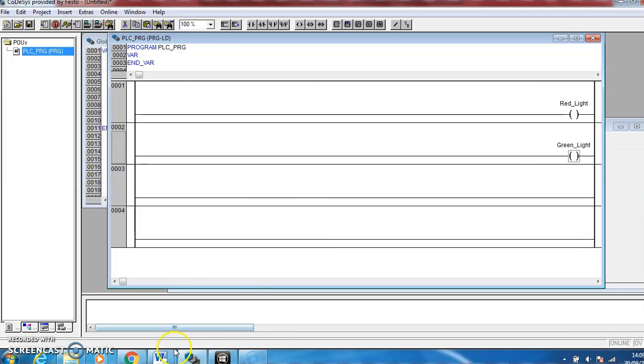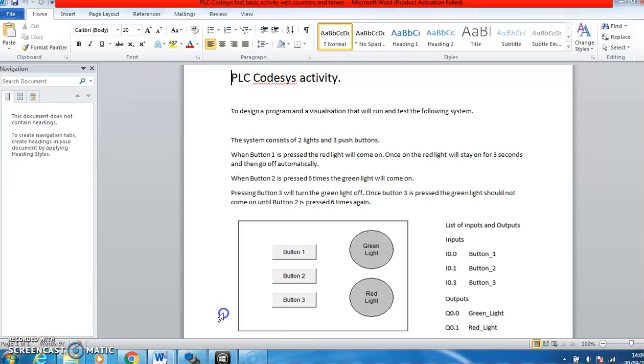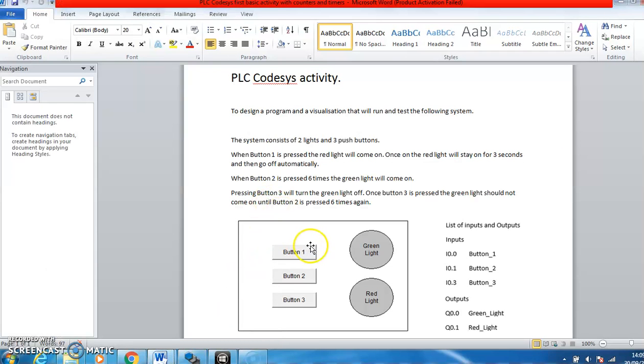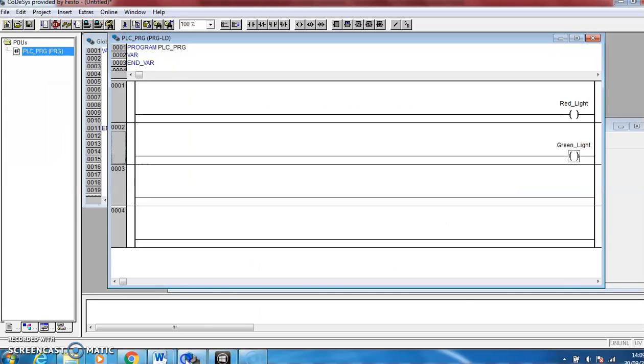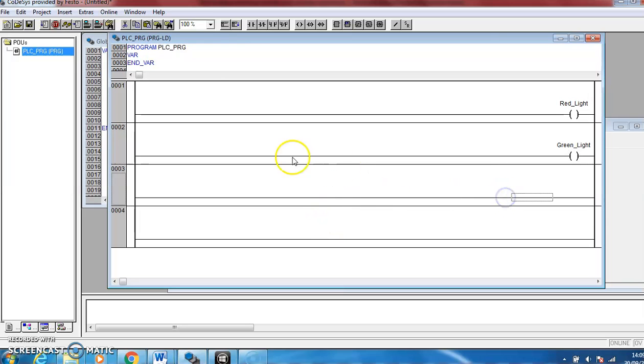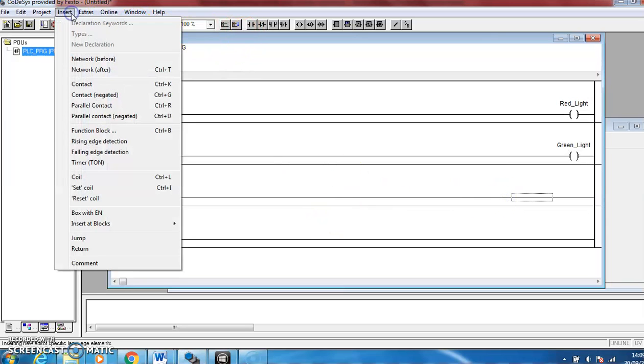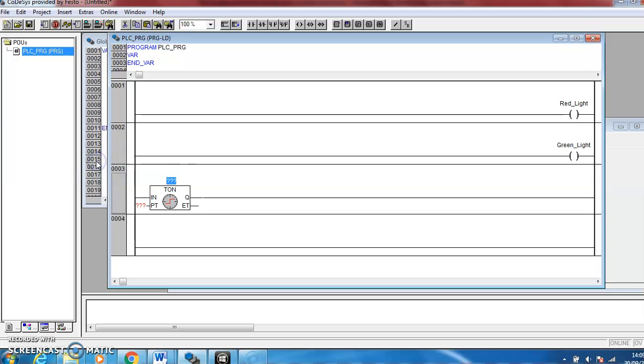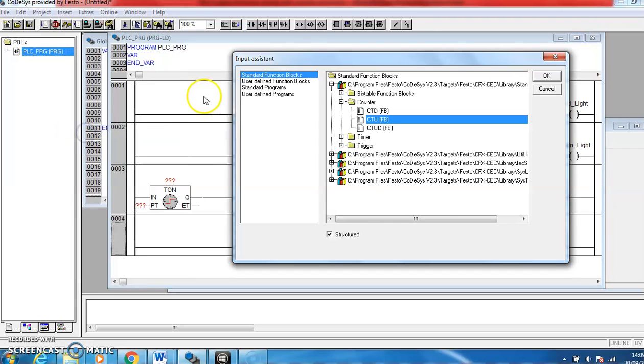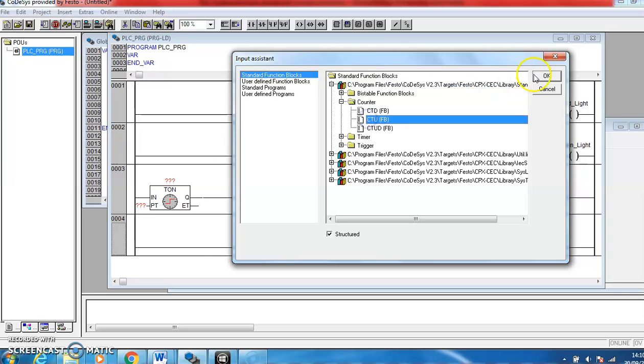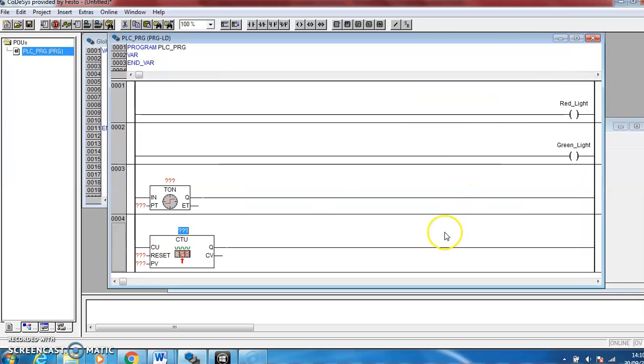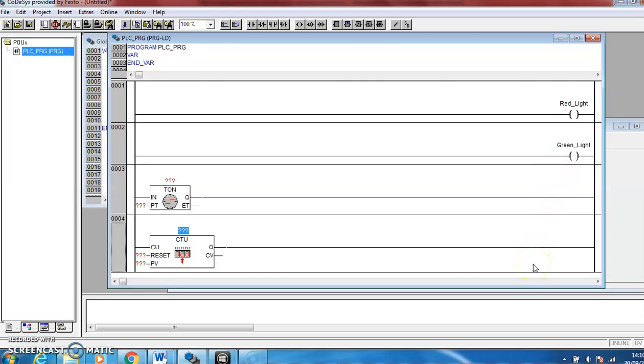And if we go and look at our system, it mentions here the red light must stay on for three seconds, so that means we need a timer. And it also says that a button must be pressed six times, so we need a counter to count those presses. So I'm going to go back to the program again, I'm going to put a line of code in for an on delay timer and a line of code in for a counter. You can get these in function blocks, counter I'm looking for a CTU which is an up counter. So that's all the lines of code I need.